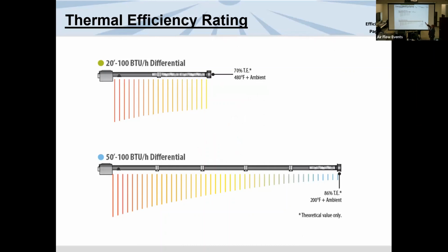There you go. I beat this kind of death, but on that 20-foot, 100,000, you're right at the minimums for certification allowance, but look at the heat pattern. If you're working over a restaurant patio, a 20-foot heater may be better, even though the efficiency numbers aren't good. The heat pattern is much better, okay? Versus a very high efficient heater. All we did here to get the efficiency up was that pipe. Didn't change anything, we just had it.